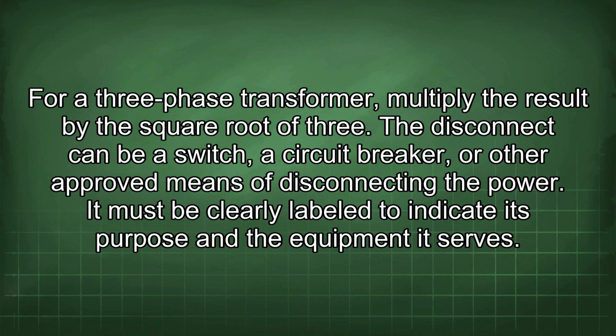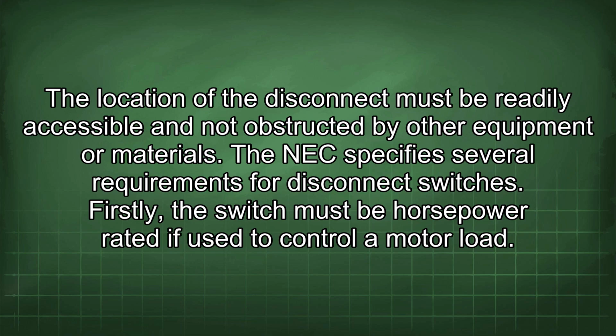The disconnect can be a switch, a circuit breaker, or other approved means of disconnecting the power. It must be clearly labeled to indicate its purpose and the equipment it serves. The location of the disconnect must be readily accessible and not obstructed by other equipment or materials.